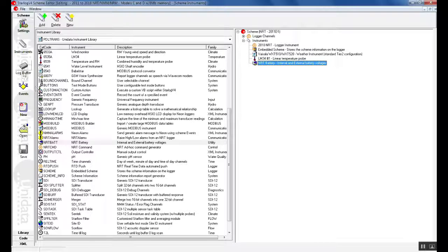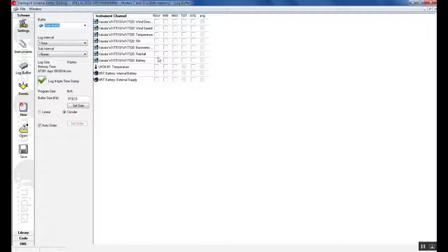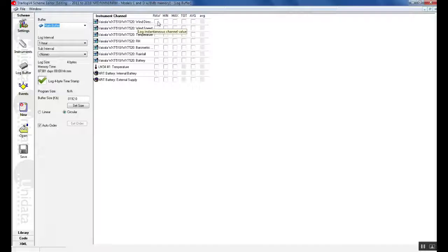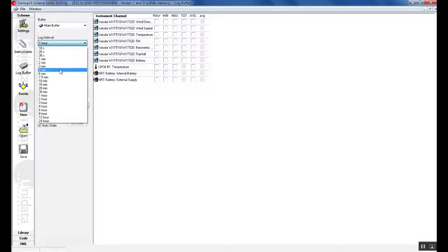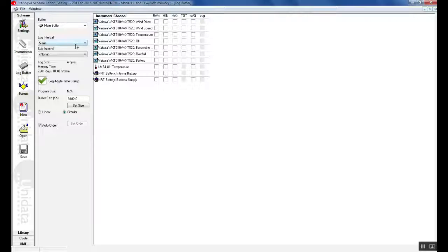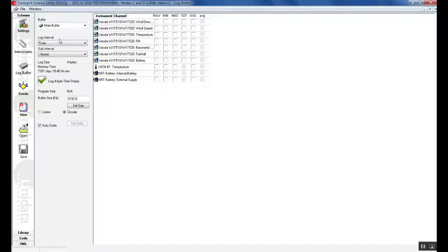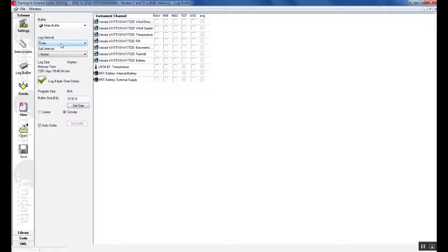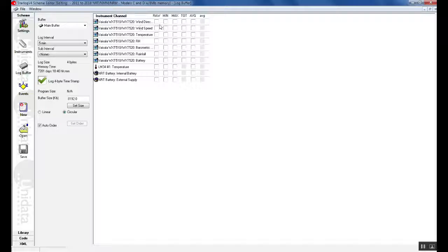The next step is to go to our log buffer. In our log buffer we select what we would like to record. There are many options. We can select raw which is the value that is recorded at the time of the log interval. So for example if we had our log interval of 5 minutes then our raw value will be the reading taken at the 5 minute point. Our minimum value would be the minimum value of all the 10 second readings over the 5 minute interval. The total is the total of all the 10 second readings over a 5 minute interval and the average is the average of the 10 second readings over a 5 minute interval. In this case we will select raw as we are only reading an SDI 12 instrument once every log.